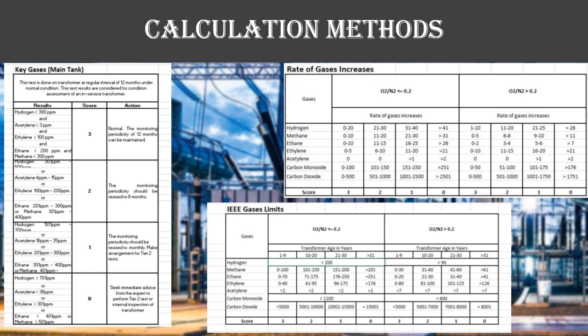So you can see over here we have the key gases main tank, we have the rate of gases increase, and then we have the IEEE gases limit. All these variables need to be put in at every single point, and every one needs to be measured by particular parameters before you can compute the overall health index of the transformer.